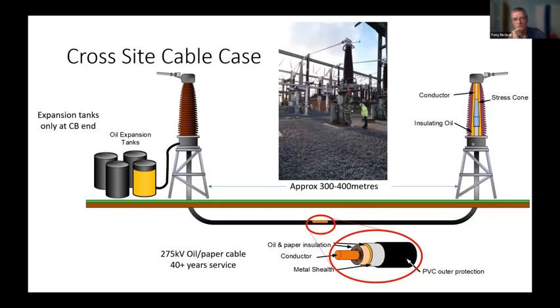So many years ago, I did work at National Grid in the UK, substation specialist, transformers, breakers, partial discharge, cable ends, and so on. What we're showing here is a short 300 or 400 meter cable on a particular site. And you've got a guy looking at the cable sealing end there. And the cable is one of those oil paper construction with lots and lots of layers, PVC outer. It's a 275 kV cable. It's been in service for more than 40 years. Nice piece of cable. It does its job, does its work.